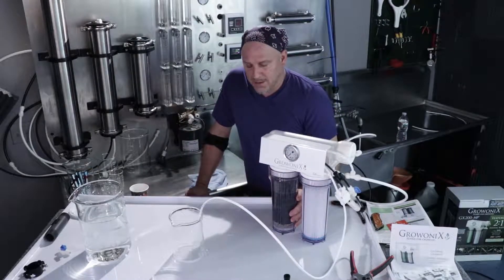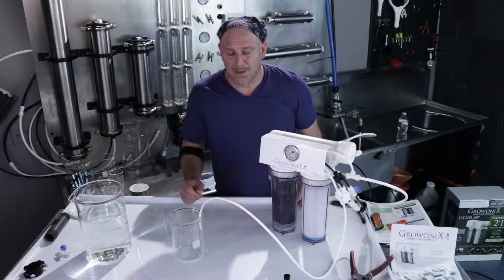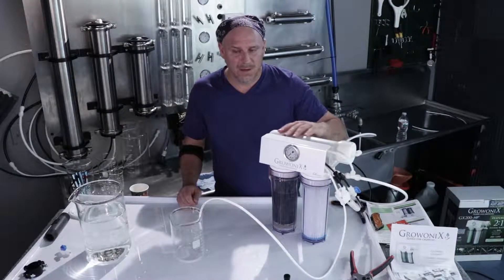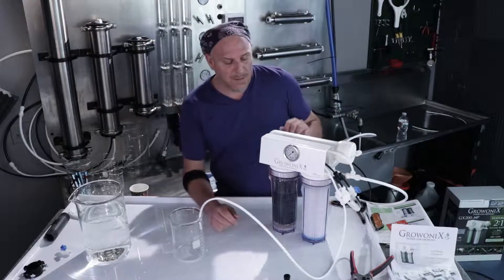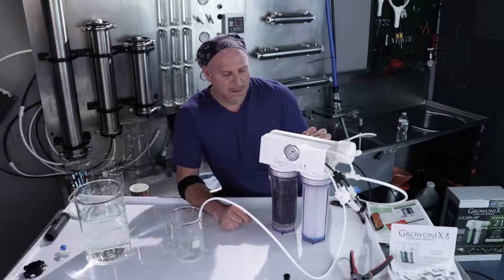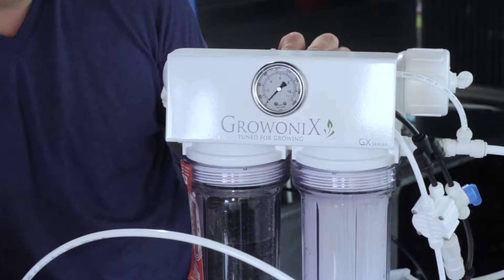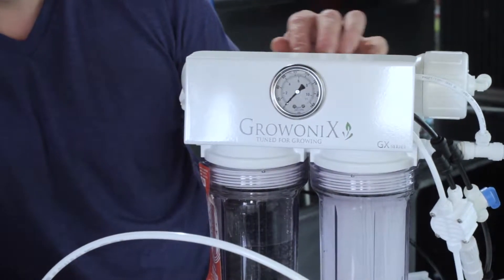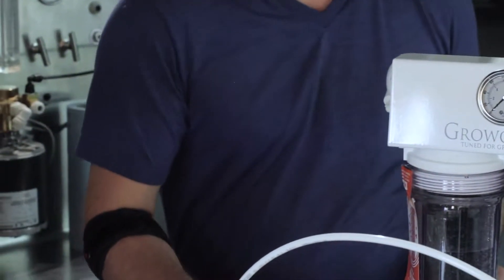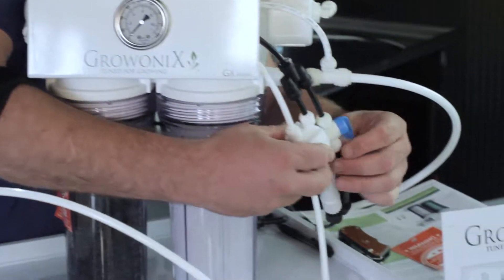Once again, when I turn the water pressure on, I'm going to turn it on very slowly. The membrane still has a lot of air in it. We want to purge all the air out of the membrane. The membrane also has some storage solution in it, usually a food grade glycerin-based storage solution, and we want to flush that out too before we use the product water.